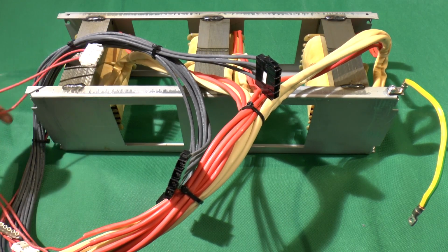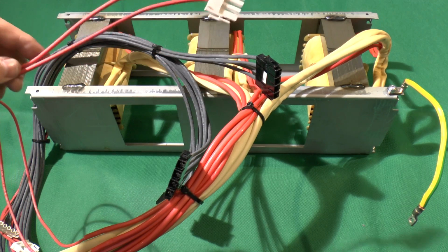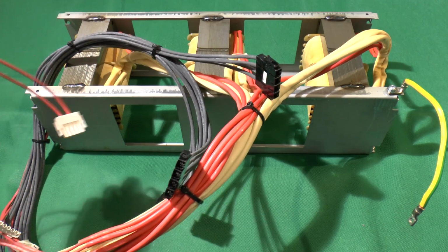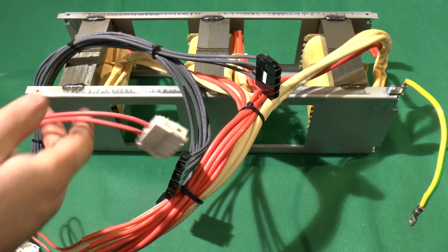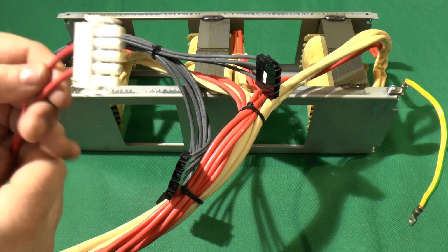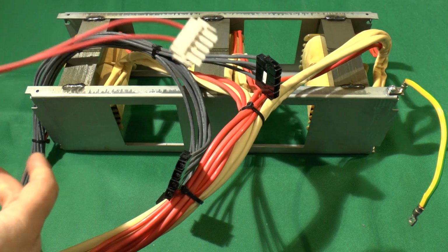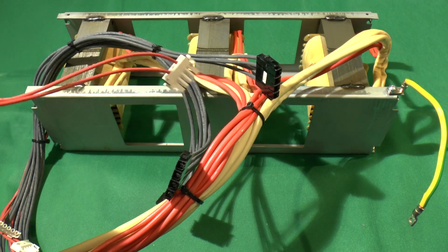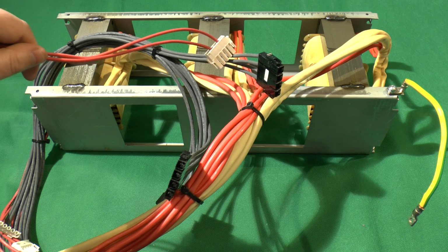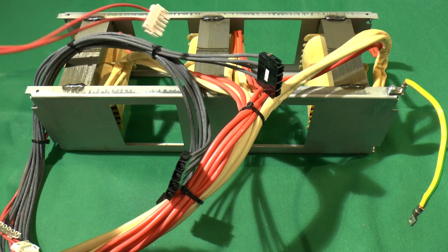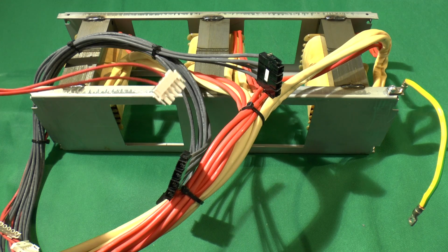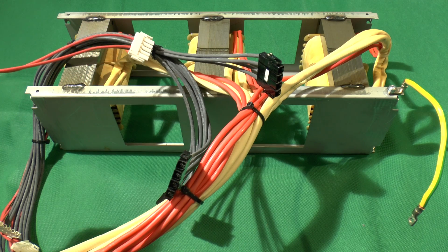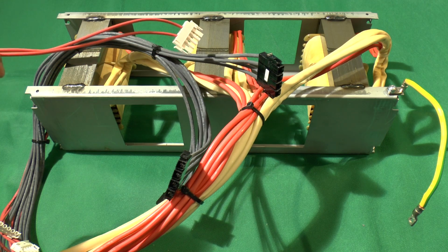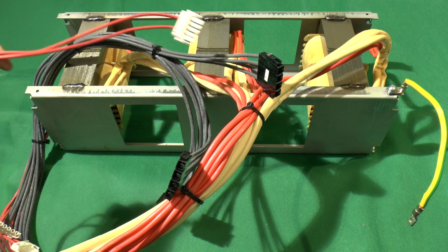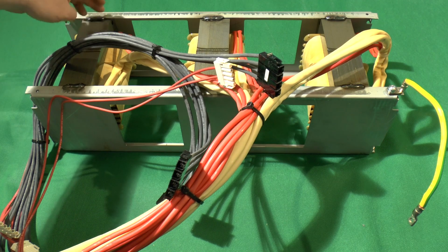But it's a 1:5 turns ratio with this supply, with this connection as well, and again there's one on each. If you put, for example, a 300 volt supply on this, depending on the polarity in relation to the input supply, you could add or subtract 60 volts from the 400 volts phase-to-phase supply. So you can go from 340 volts up to 460, and you'd still get a nominal 400 volts on the bus.